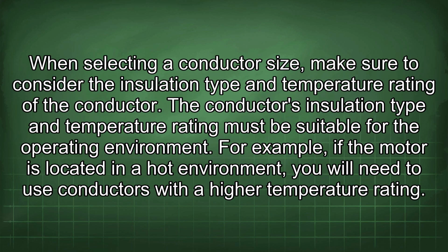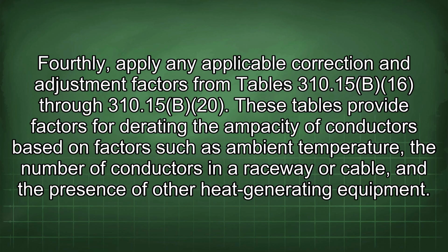When selecting a conductor size, make sure to consider the insulation type and temperature rating of the conductor. The conductor's insulation type and temperature rating must be suitable for the operating environment. For example, if the motor is located in a hot environment, you will need to use conductors with a high temperature rating.